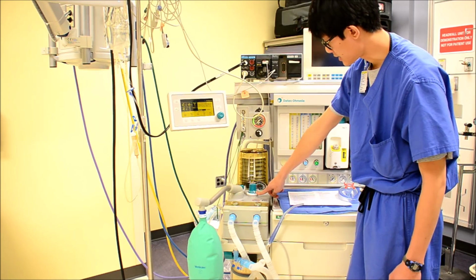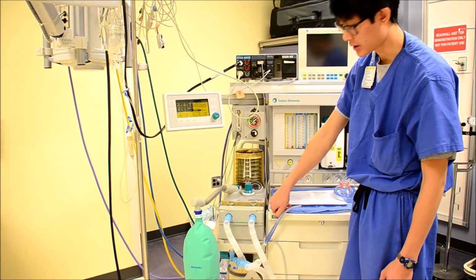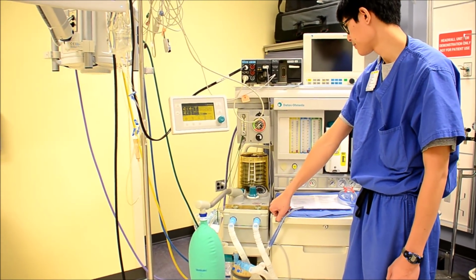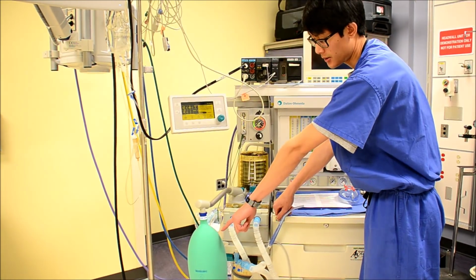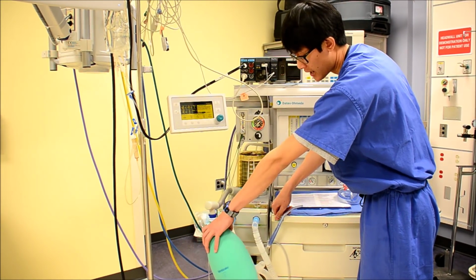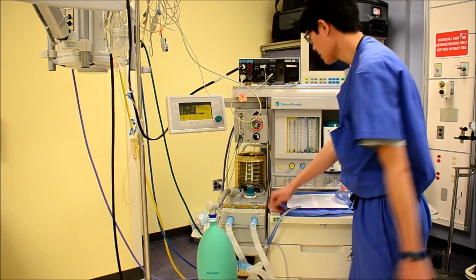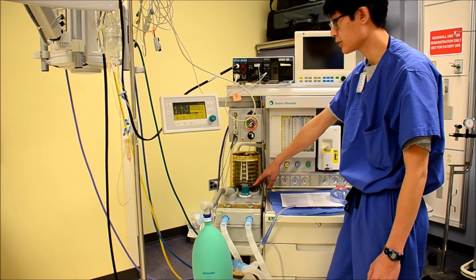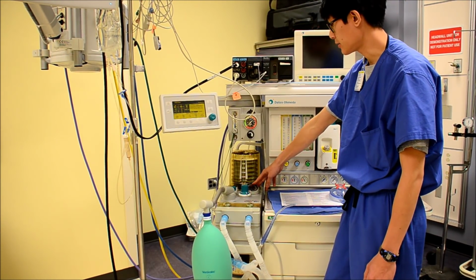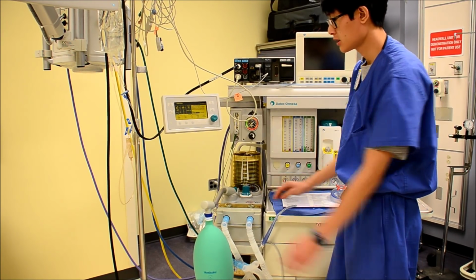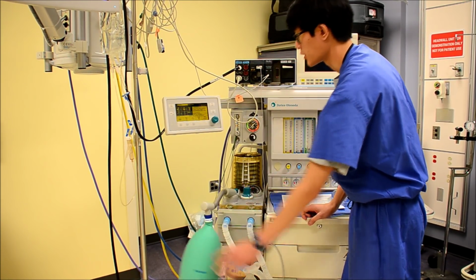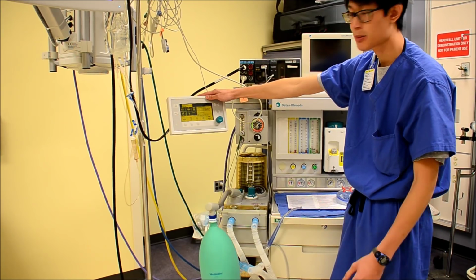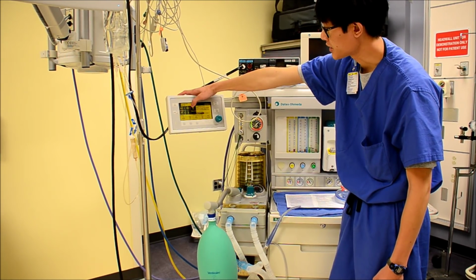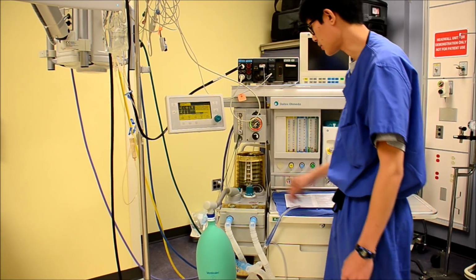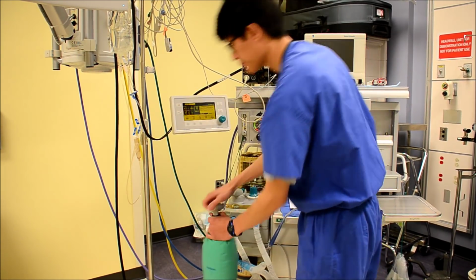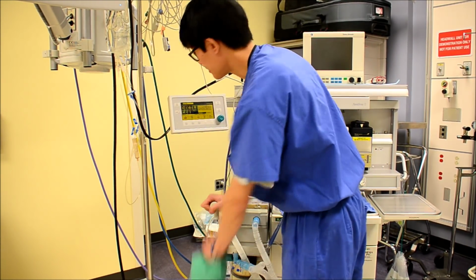Once you reach 70 and your APL valve is closed, go ahead and hit your O2 flush button. You'll see your circuit bag fill, and you're going to see if your pressure will hold to 30 centimeters of water. That ensures that there's no leak in the system. And you check to make sure it has your high pressure alarm, and you've oxygenated to 100% oxygen. Once you've done that, you can release the pressure, and we're going to check the ventilator now.